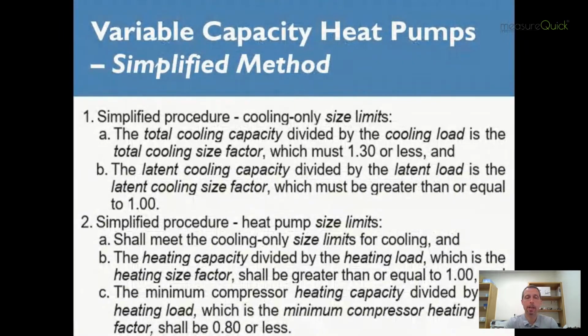So if I skip ahead a slide, what I'm showing you are some excerpts and the footnotes to that table. When we're looking at step 2, the simplified procedure for heat pump size limits, it basically spells it out for you. We've got to meet the cooling only size limits for cooling, and note the word and, the heating capacity divided by the heating load, which again is your basic Manual S criteria to determine sizing factor, must be equal to or greater than 1.0. This means that we're providing 100% of that output that we talked about there. But we also need to look a step further. We need to figure out the minimum compressor heating capacity divided by the heating load and make sure that it's less than 0.8.